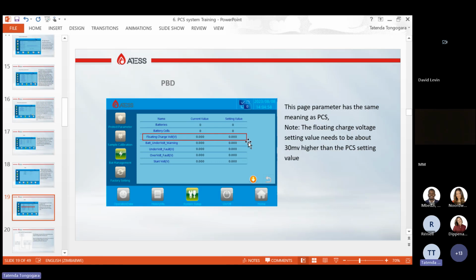And then float charge volt. If your PCS has a float charge of 3.5, this one can have a float charge 30 millivolts, 50 millivolts higher. I've seen that 50 millivolts higher works best. So if you have 3.5 float charge on the PCS, on the PBD it should be 3.5 plus 0.05. That's your 50 millivolts, so it should be 3.55 for efficient charging of your system.